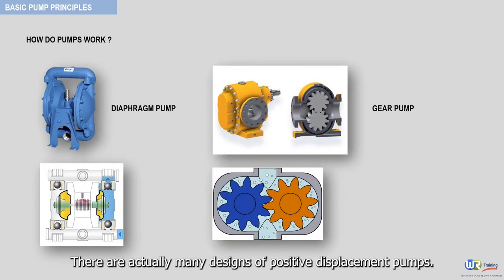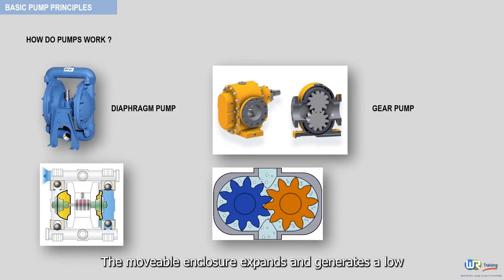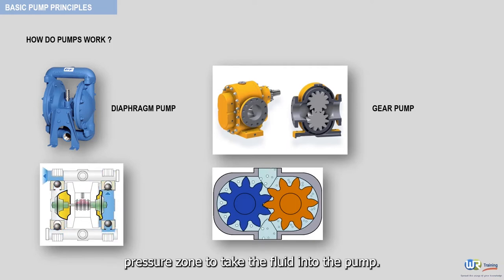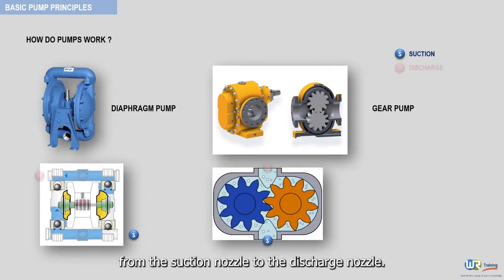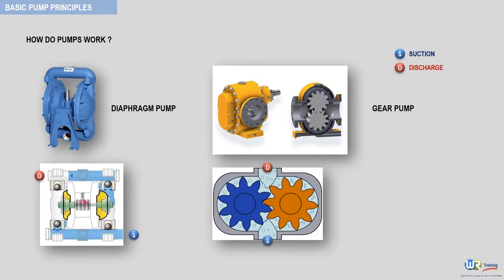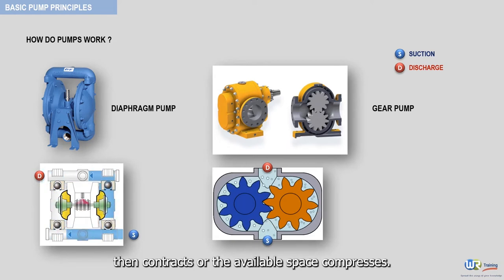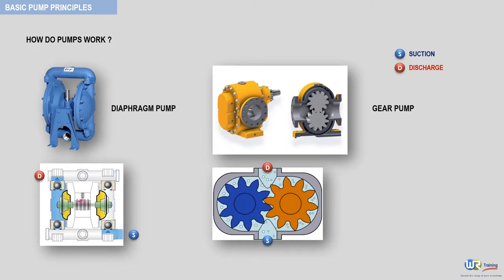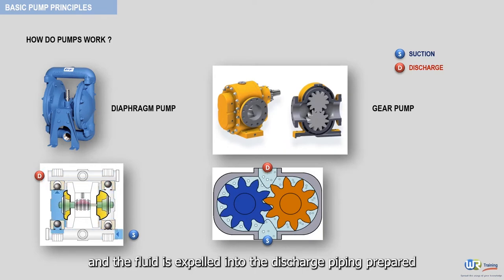There are actually many designs of positive displacement pumps. The movable enclosure expands and generates a low pressure zone to take the fluid into the pump. The captured fluid is physically transported from the suction nozzle to the discharge nozzle. Inside the pump, the expanding movable enclosure then contracts, or the available space compresses, generating a zone of high pressure inside the pump.